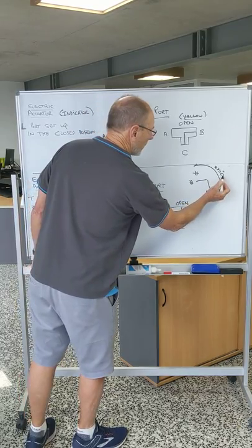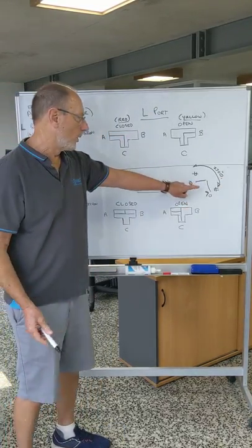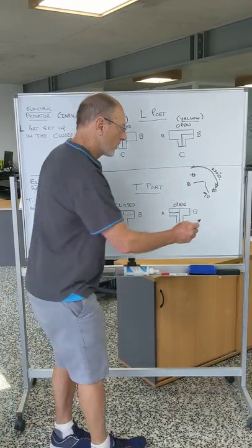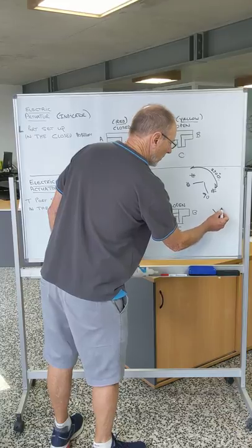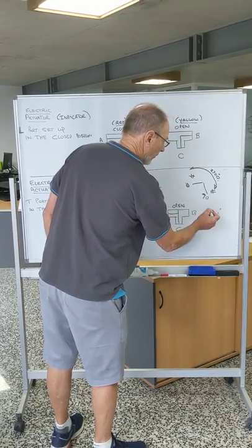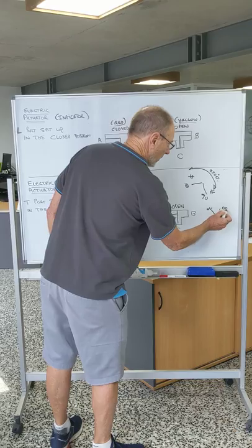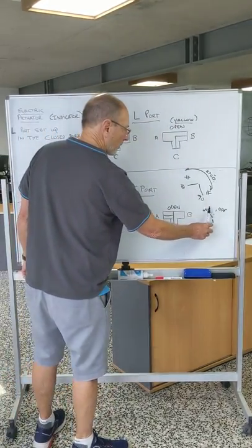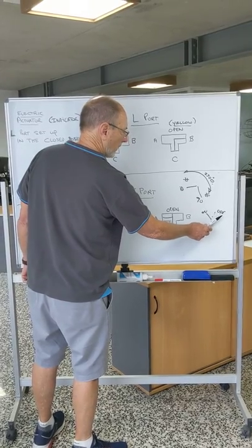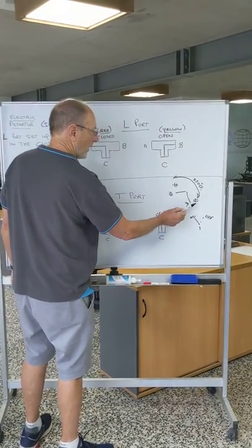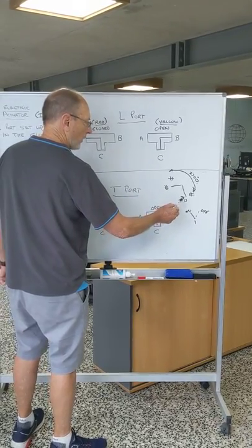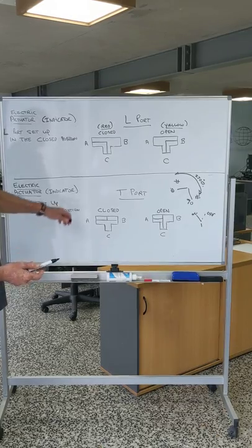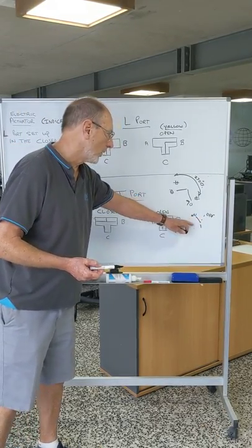The suggestion is, if it does go into this area, to reset it. Take your external switch to your on-off switch and your external power supply. Put your power back on, switch this in one direction, leave it there until the rotation takes place, switch it back in the other direction, and the unit will rotate right around and reset itself automatically in the position that you want to set your switch at.